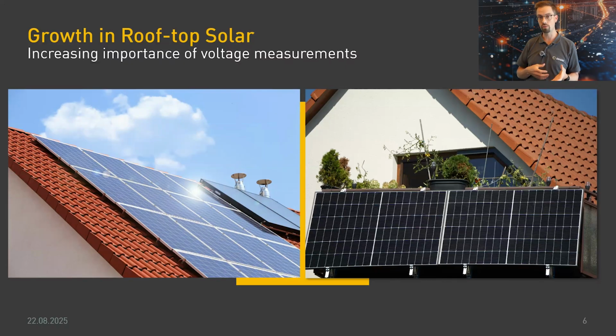Now this isn't just a voltage rise problem, there's also voltage drops, and it happens in exactly the same way. If you imagine lots of EVs charging or lots of heat pumps running, each one incrementally drops the voltage along the line. So at the very furthest point in the grid, that's where it's most interesting to look at what the situation is. You might think, okay, I don't need this because I don't have much solar in my grid. But if you have quite a lot of, say, winter load in your grid, this could equally be an issue you might see in terms of voltage drops.